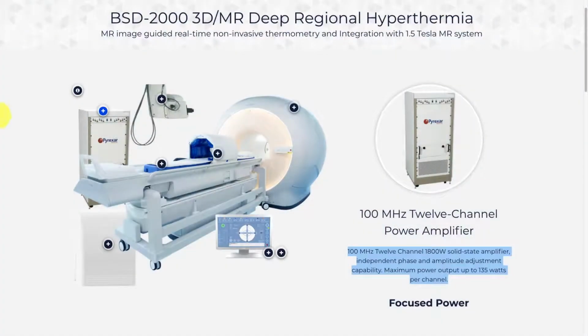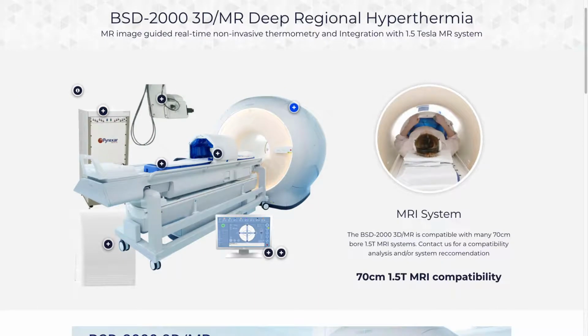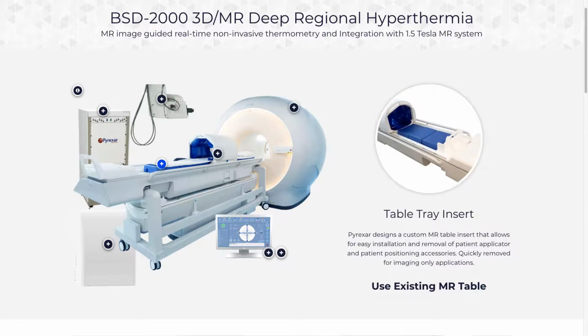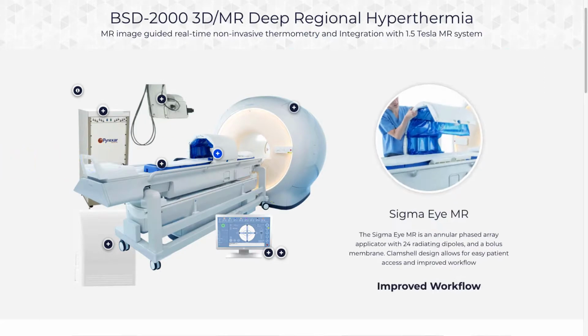The BSD-2000 3D MR Deep Regional Hyperthermia System, the first image-guided real-time hyperthermia system with non-invasive thermometry. The BSD-2000 3D MR is compatible with many 70 centimeter bore 1.5T MRI systems. Please contact us for a compatibility analysis or system recommendations. Pyrexar designs a custom MR table insert engineered for easy installation, allowing for quick removal for imaging-only applications. The Sigma Eye MR is an annular phased array applicator with 24 radiating dipoles and a bolus membrane. The applicator design allows for easy patient access and improved workflow.